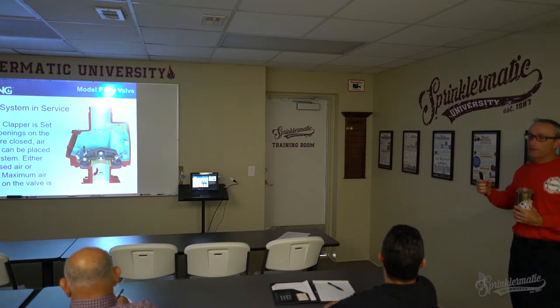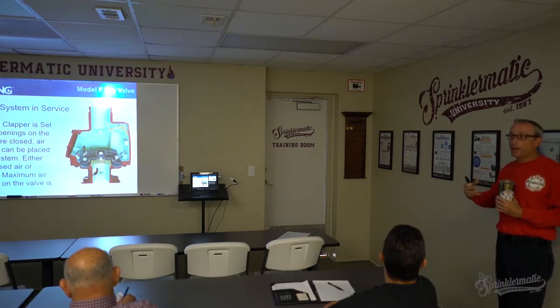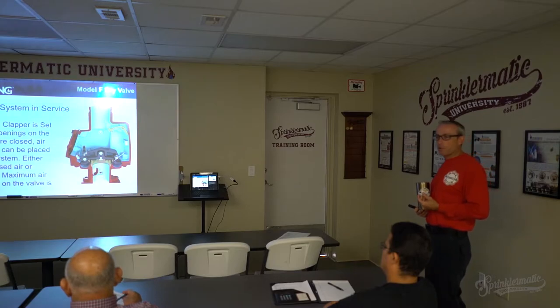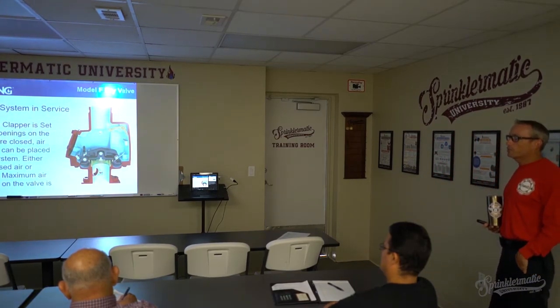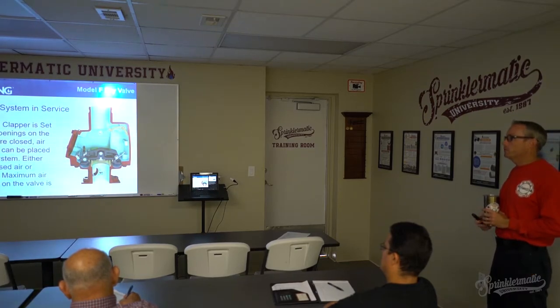There is evidence of, it's called MIC, right? Even in dry systems, there's still evidence of MIC, because if it's compressed air, you're going to have a little bit of moisture in there. You're going to generate the... what's it stand for? Microbiologically induced corrosion. That's right. So a lot of the systems are starting to move more towards nitrogen because there's a lot less chance of that developing with nitrogen systems.